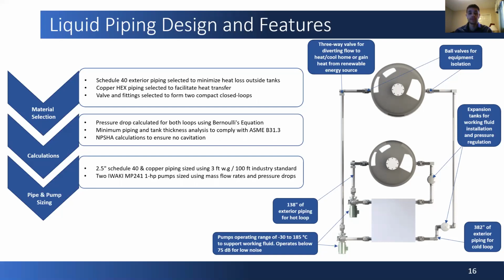For sizing, 2.5-inch pipes were selected, and this was done by using the 3-foot water gauge per 100 feet industry standard, as well as the mass flow rates we already calculated. For pump sizing, we used the mass flow rates as well as the total pressure drop in the system to select relevant pumps. 2 1-horsepower pumps were selected.